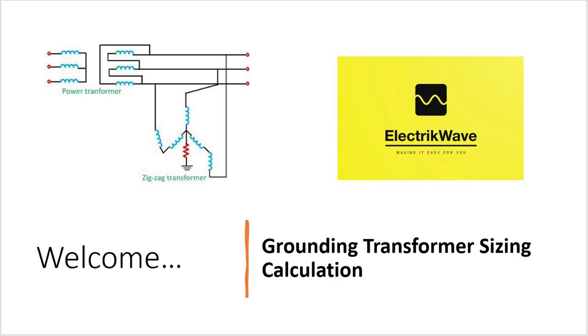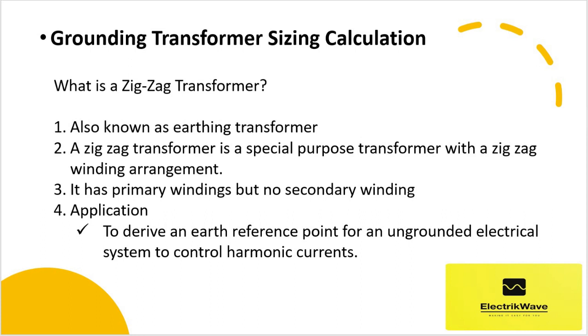Welcome. Let's see grounding transformer sizing calculation. First, let's understand what is a zigzag transformer — it is also known as an earthing transformer. A zigzag transformer is a special purpose transformer with a zigzag winding arrangement. It has primary windings but no secondary winding; however, sometimes a secondary winding is also provided for auxiliary power supply applications.